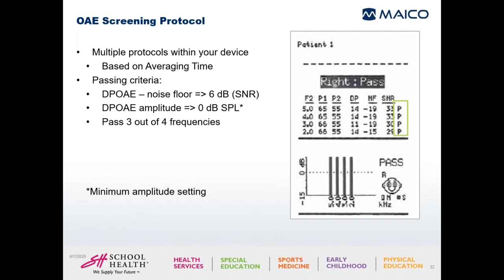So just be observant to those types of things within the screening of that particular child. And then we also get a lot of questions about, what about PE tubes? With most devices, there can be a setting that you can bypass a portion of it to continue on testing a child that has PE tubes. What I would recommend, though, is to start as you normally would. If you know that child has a PE tube, I would just start as you normally would and perform the measurement. Only if you're picking up problems would I resort to the process that the manufacturer recommends of bypassing this calibration portion of the test to be able to continue conducting the test even with a PE tube in place. So OAEs can be done even if PE tubes are in place.